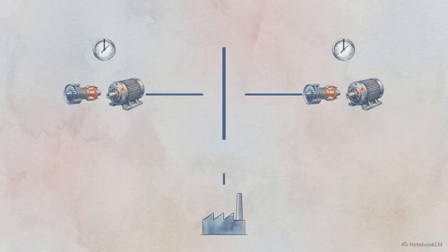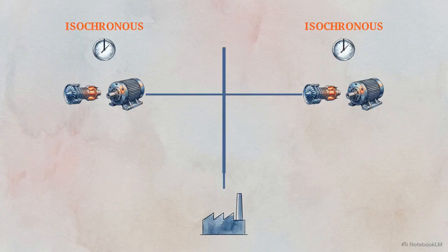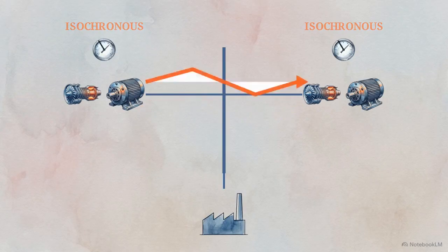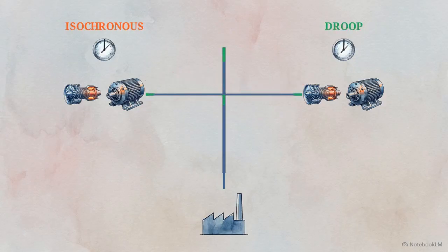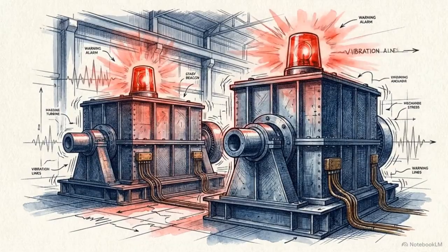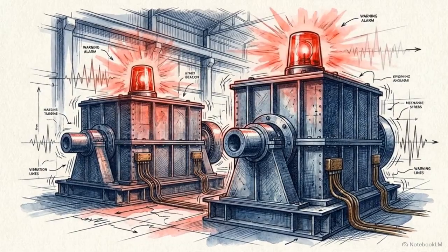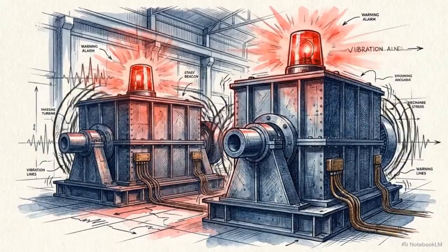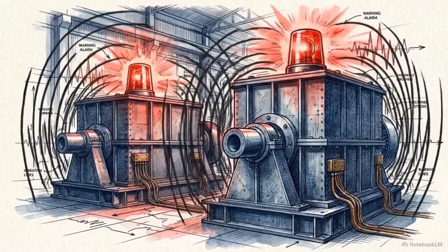Here is a real-world diagnostic scenario for field engineers. This diagram shows an actively hunting grid, with power oscillating wildly between units. The operational fix is clear. Either verify the active load-sharing networks or reconfigure the parallel governors to droop mode to stabilize the flow. In a multi-unit power plant, perfect control is the enemy of stability. Two independent anchors equal a fight. Steady-state electrical stability keeps the plant running.